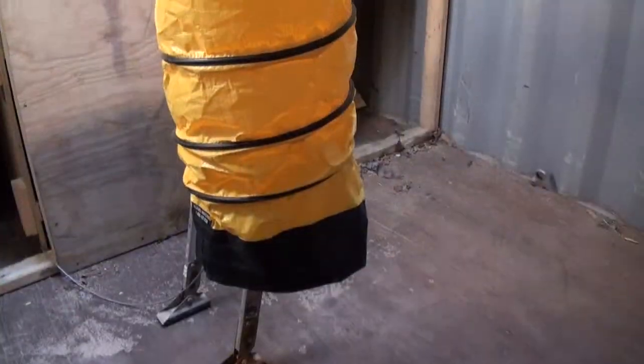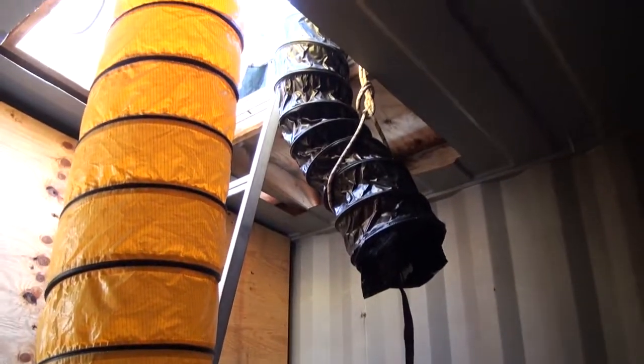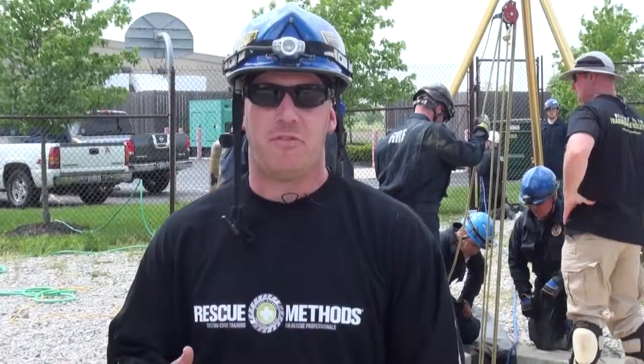All right, so if you've elected to use positive and negative pressure, maybe the opening in the space allows it, or you've identified that that's the operation that you need to go into, again, we're going to begin by identifying the contaminant that's in the space. So we're going to try to figure out what the R-gas D is of that item. If it's going to be a contaminant that's lighter than air, and our contaminant is all going to be in the top of the space, we are going to put our exhaust in the top of the space and draw that contaminant out. We'll then piggyback our positive pressure system in there, dropping that ductwork to the bottom, which is going to pressurize the lower areas and help push that contaminant out the top.